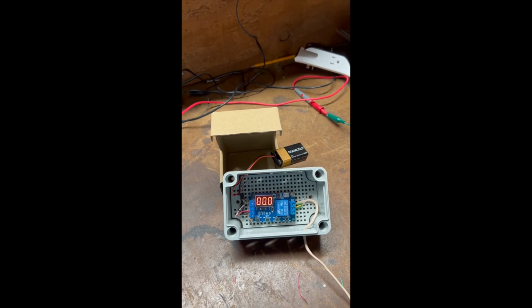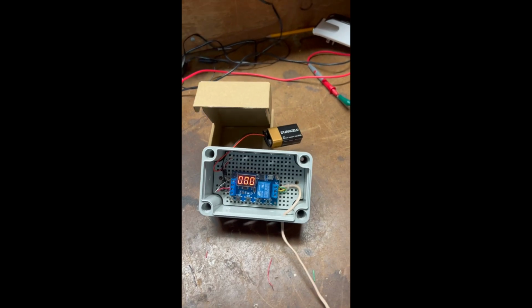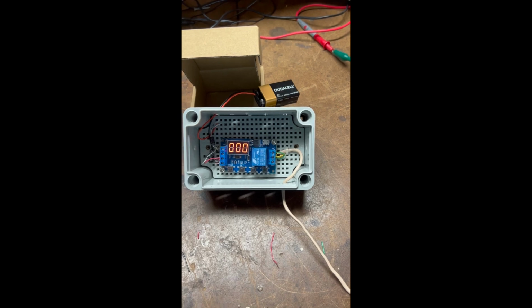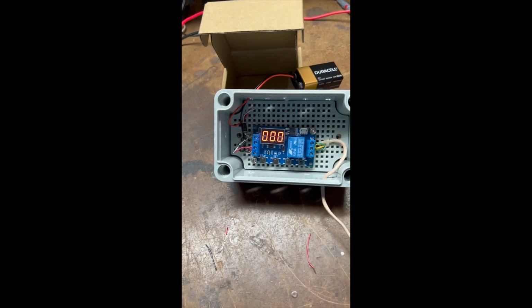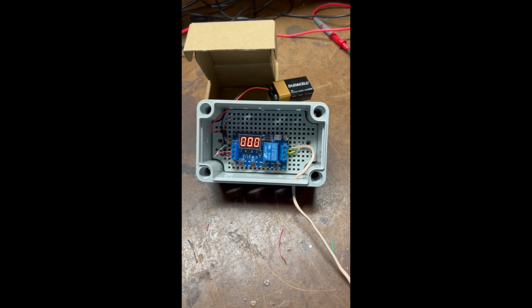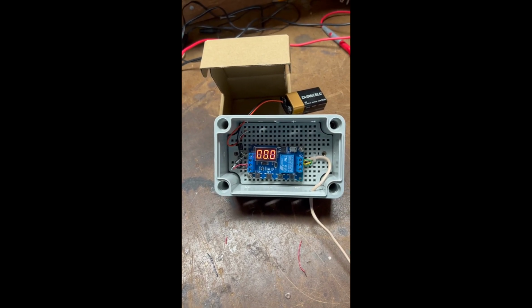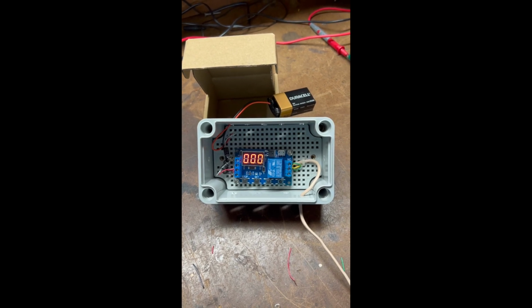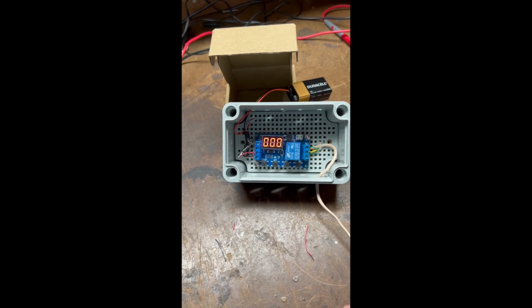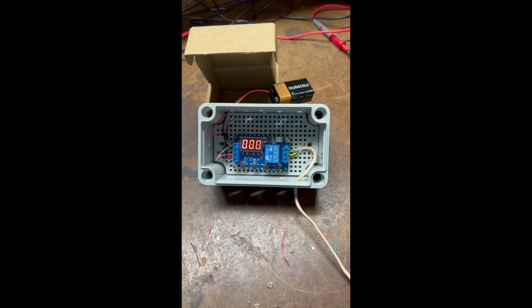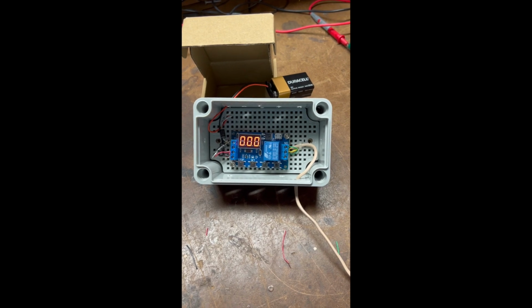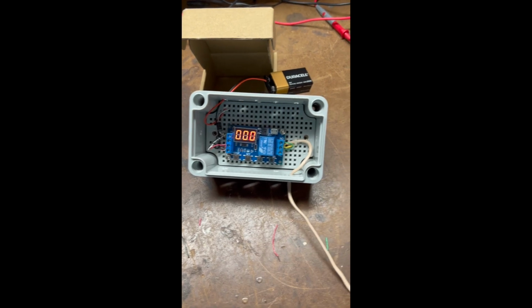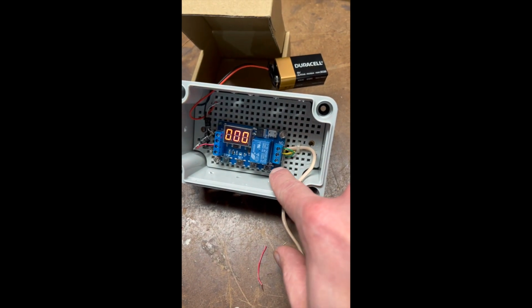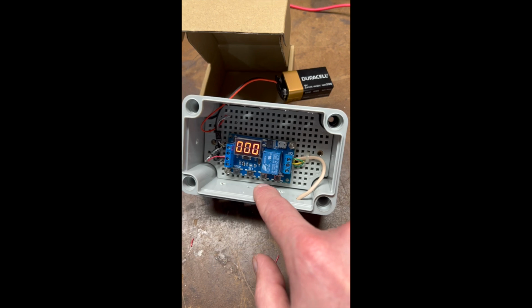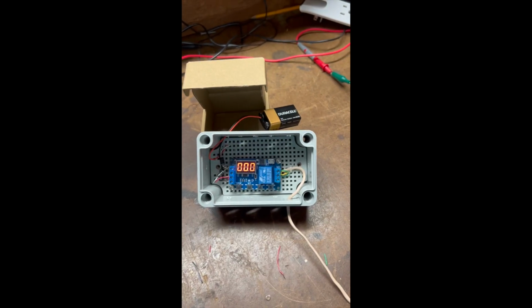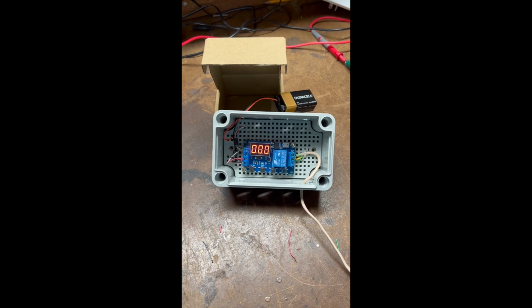And so I thought about flipping it around and saying, well, what if I use the normally open side and essentially reverse the logic so that on an alarm I'm going to close on that side by activating the relay instead of inactivating the relay. So that's what I did. And actually this timer circuit has a really cool feature where we can keep all the programming we had. All we do to do that is we go from our contacts from the normally closed side to the normally open side, and we press and hold the down key. It goes from what they call F1 to F2 mode, so essentially reverses the logic.